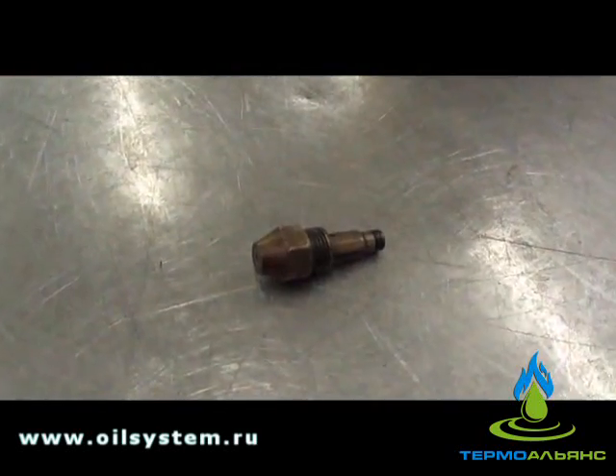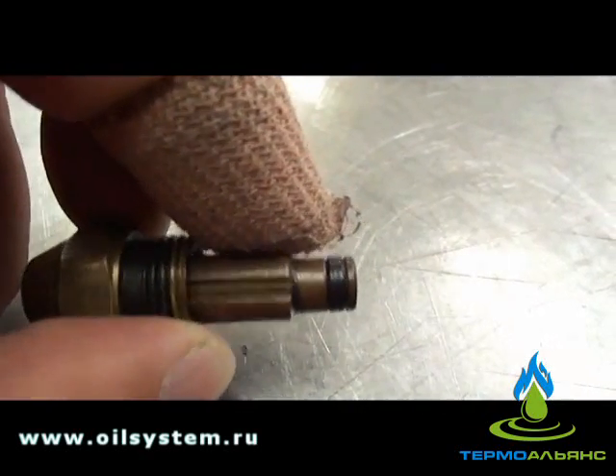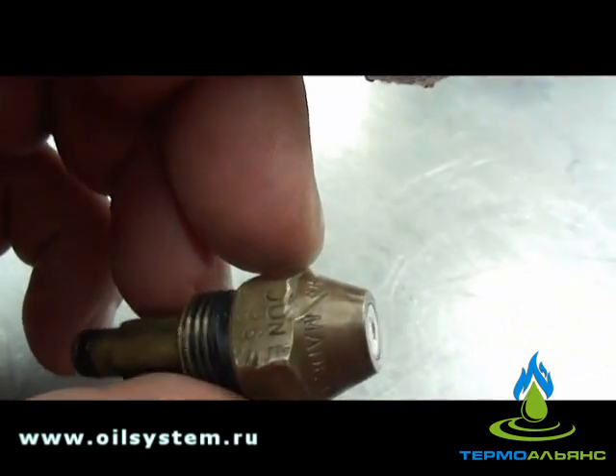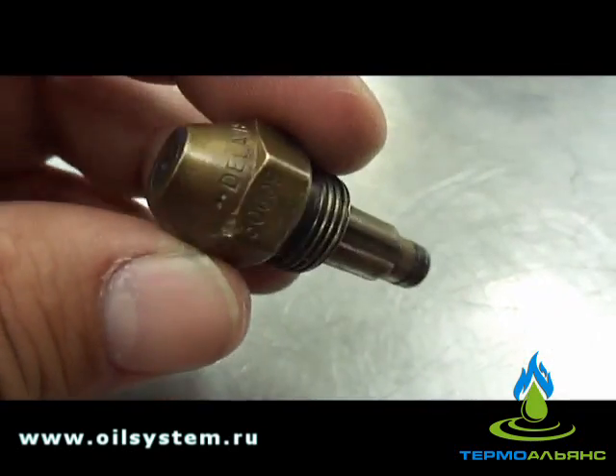Here we have an example of a nozzle that's been in use for quite a long time. The rubber o-ring is just about flattened out on the backside. It's obviously completely plugged. And if you look on this side here, it's got some wear. It's not in the worst shape, but it does have some wear. For the price of the nozzle it might make sense to replace something like this.